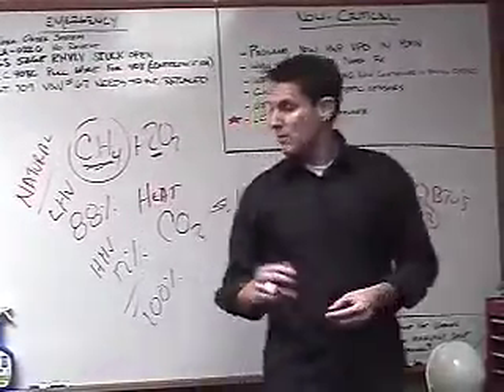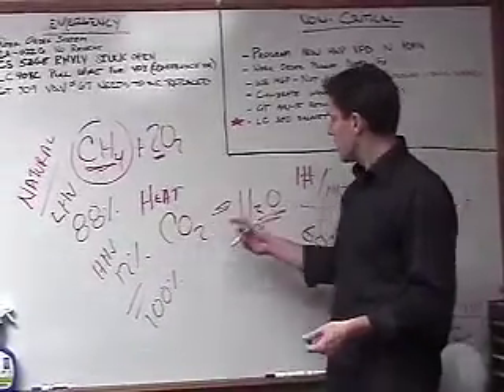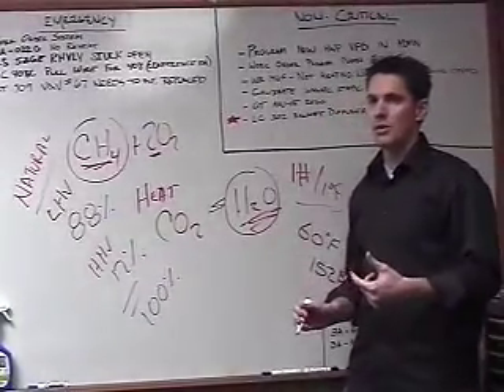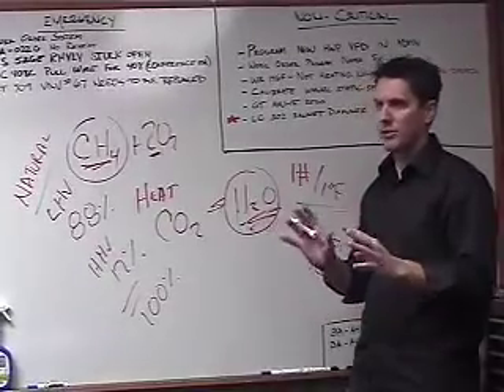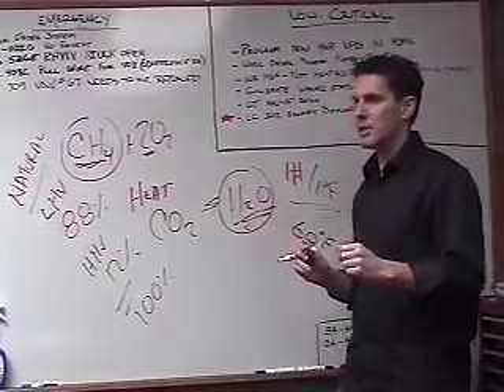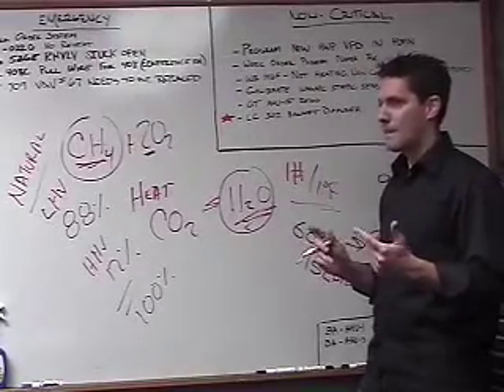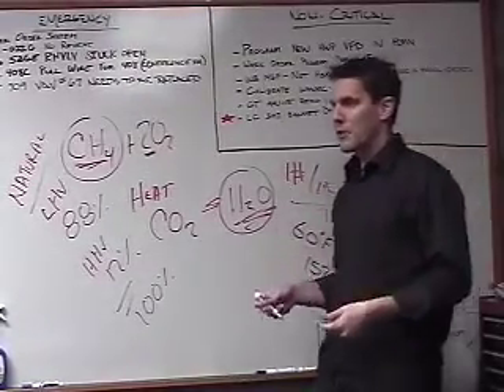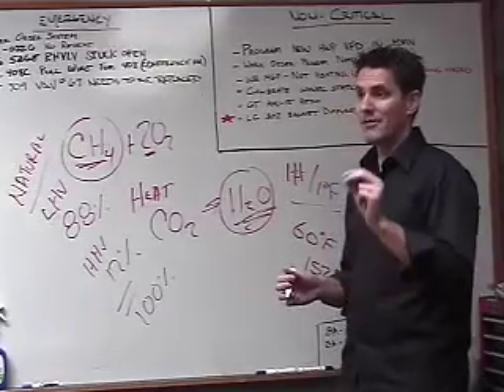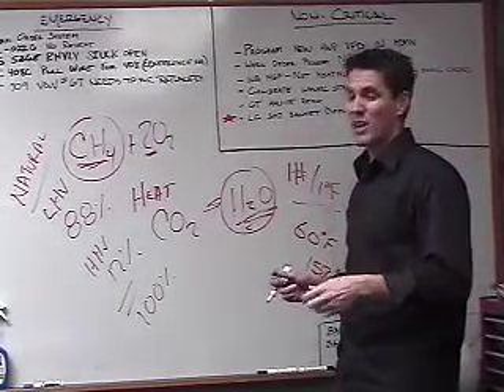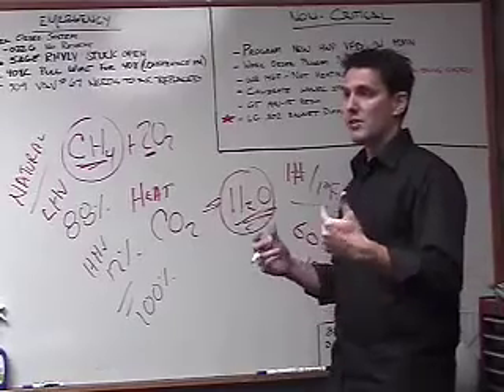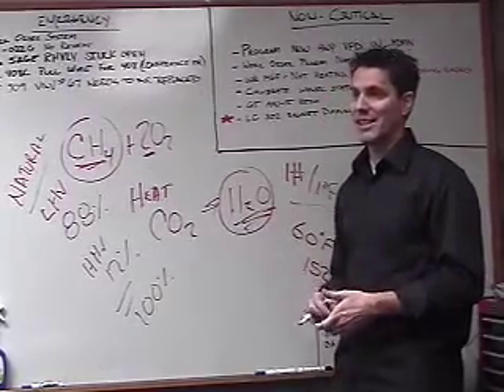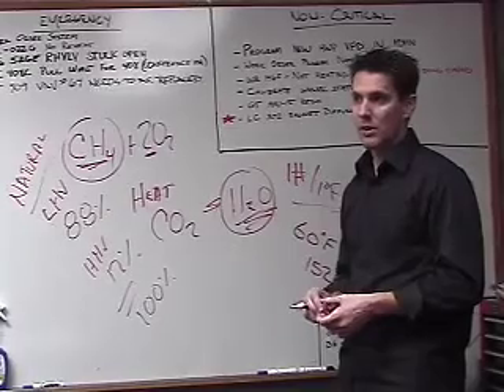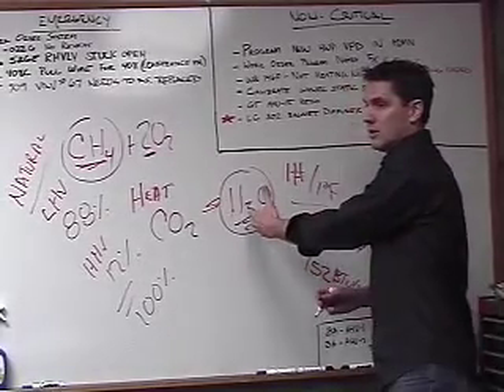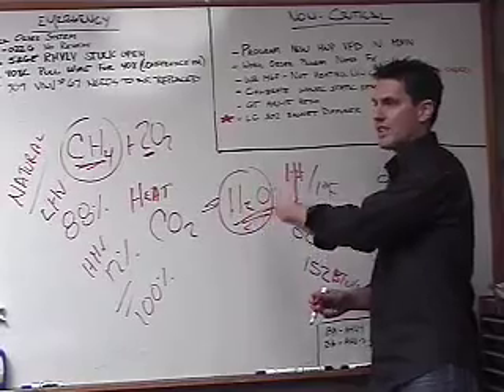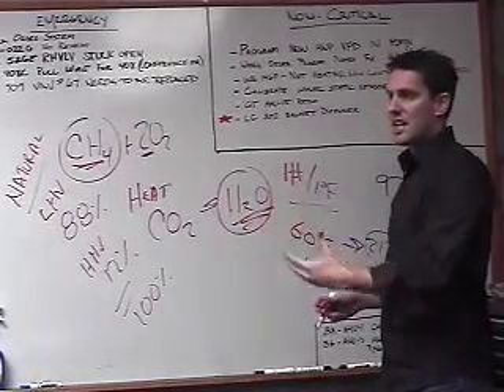Okay, now let's go back to the boiler process. In the boiler process, I'm creating a lot of H2O. What temperature am I operating at approximately on your flame? Anybody have any idea what your flame temperatures might be? You can have flame temperatures around 3,000 degrees. In fact, what we try to target when we set up our boilers is around 2,800 degrees Fahrenheit. Does water at atmospheric pressure exist at that temperature? It doesn't. So when I create all this H2O, what phase, what state is it in? It's steam, isn't it?